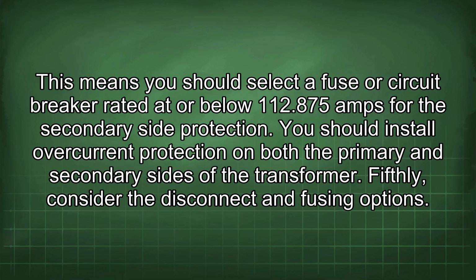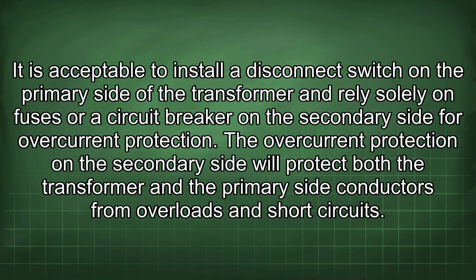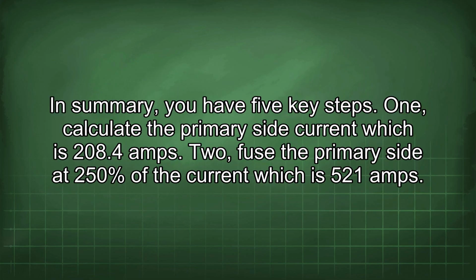Fifthly, consider the disconnect and fusing options. It is acceptable to install a disconnect switch on the primary side of the transformer and rely solely on fuses or a circuit breaker on the secondary side for overcurrent protection. The overcurrent protection on the secondary side will protect both the transformer and the primary side conductors from overloads and short circuits. In summary, you have 5 key steps.